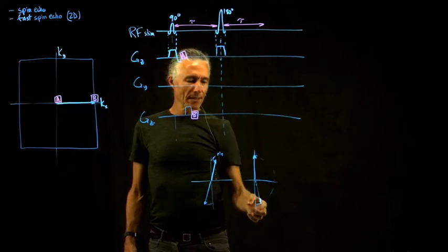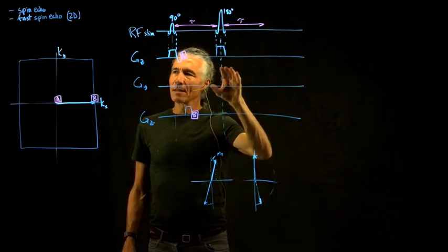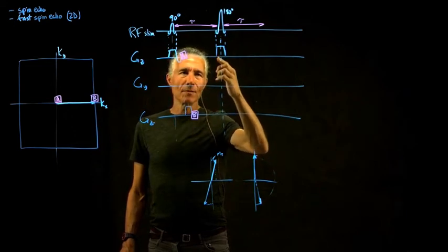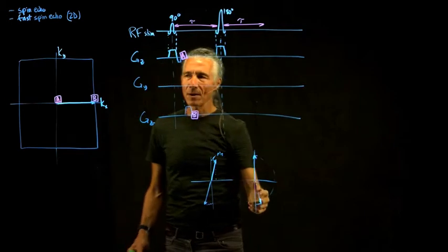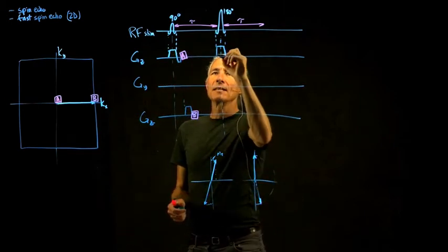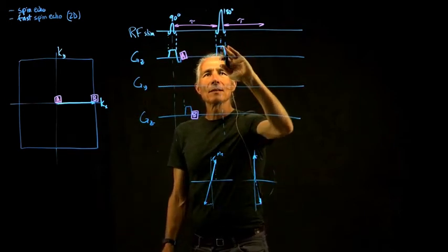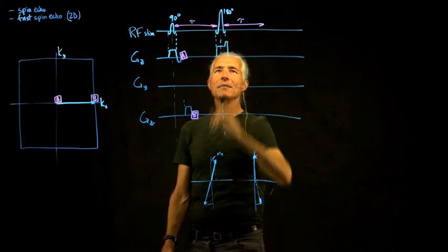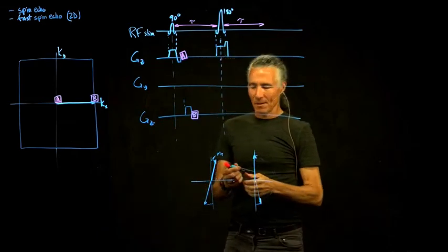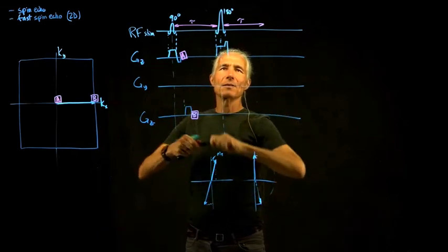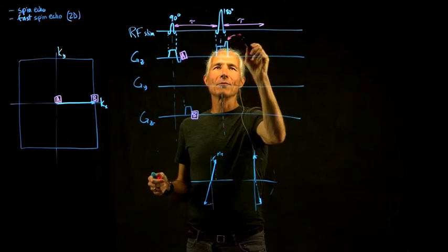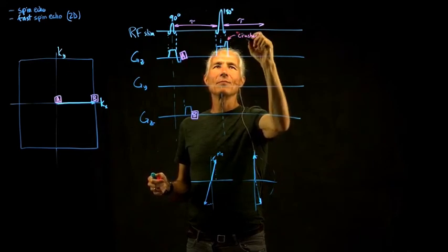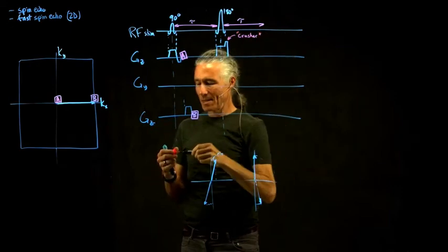if the signal, which supposedly has transverse magnetization that only came from the echo, actually has some transverse magnetization that came from our RF pulse, that's going to mess things up. And so typically what happens is you have a little horn on the slice select pulse, and this thing is called a crusher.